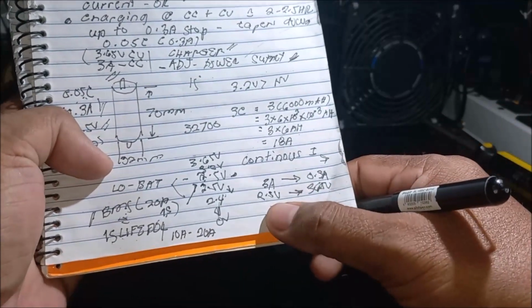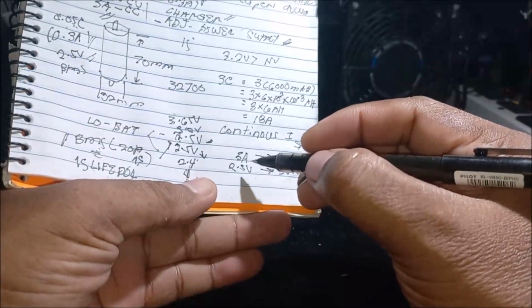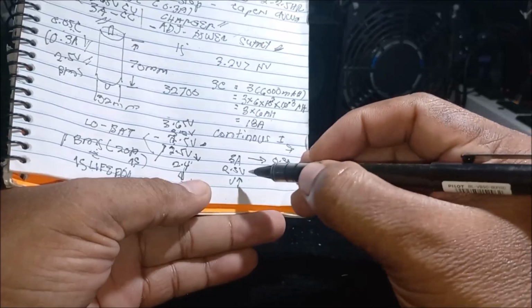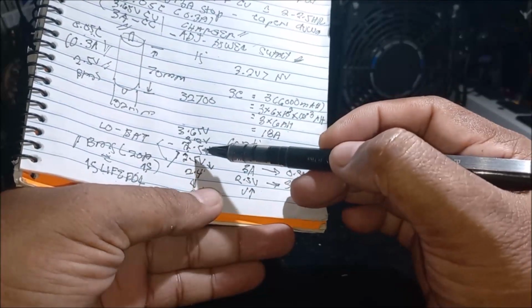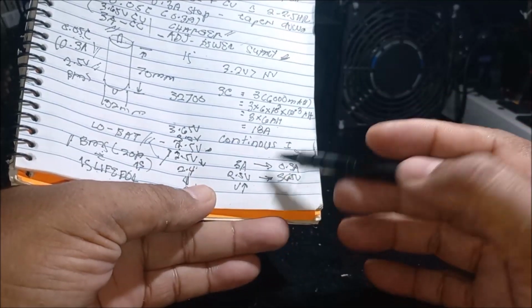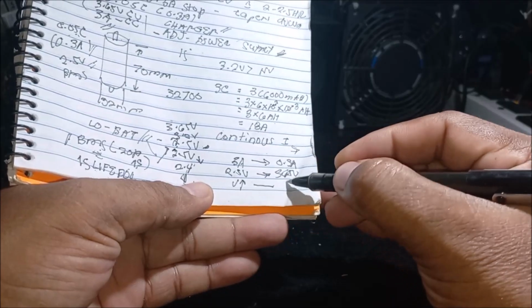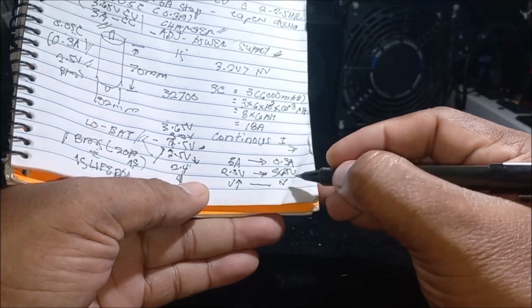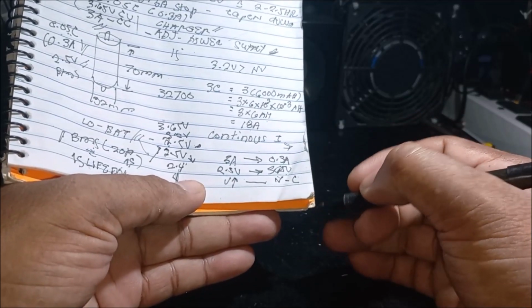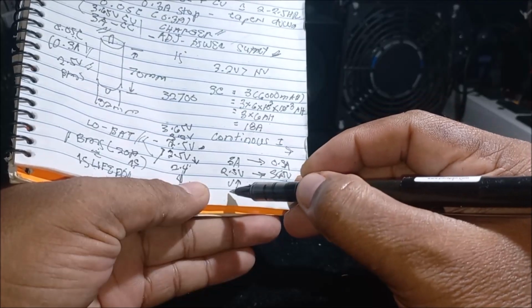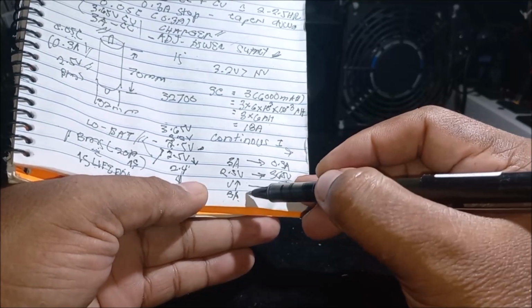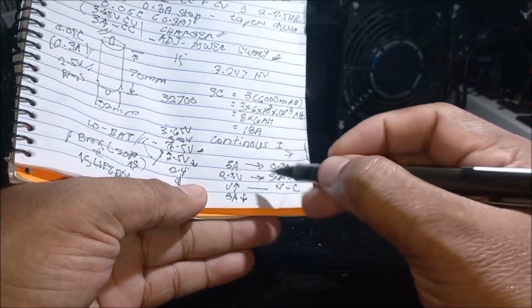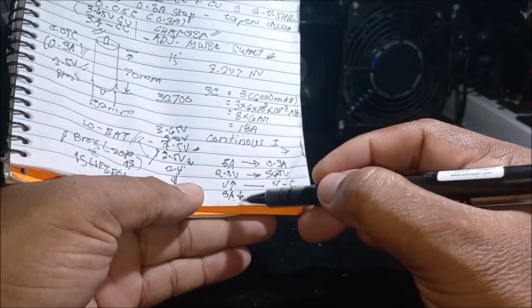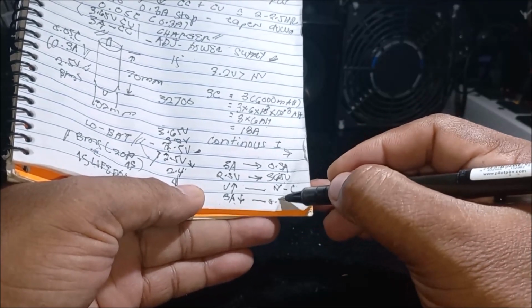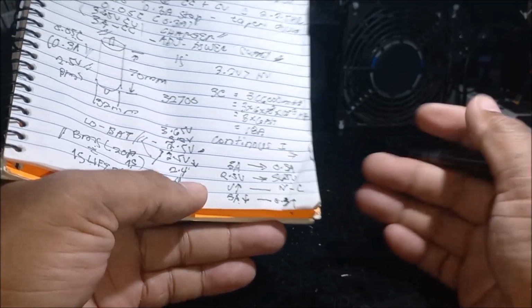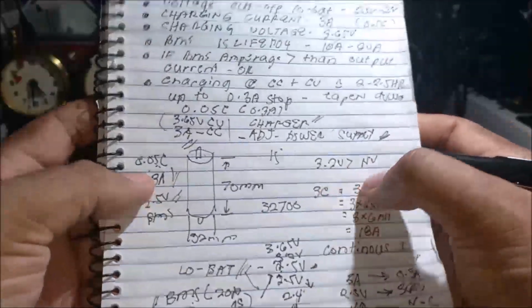The voltage is increasing while charging, from 2.5 volts, the low bat cut-off voltage, up to 3.65 volts. Once it reaches 3.65 volts, it becomes constant voltage, and the current, starting from 3 ampere, continues to decrease. So voltage increasing, current decreasing, down to 0.3 ampere, then stop. That is the process of charging and discharging.